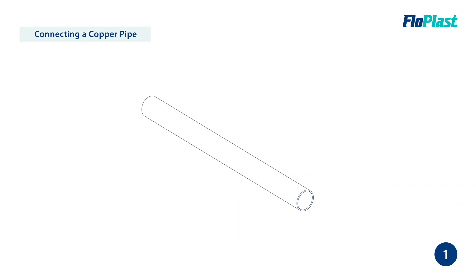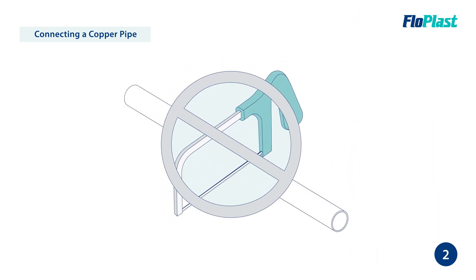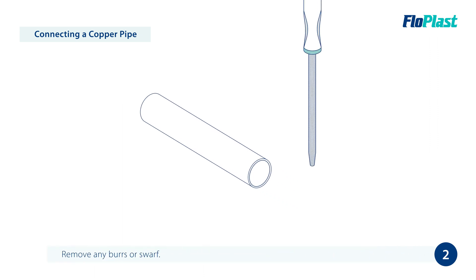For copper pipe installation, as with plastic pipe, measure and mark the required length. Cut the copper pipe using a rotational pipe cutter. Again, do not use a hacksaw. To reduce the risk of leaks, ensure you remove any burrs or swarf.